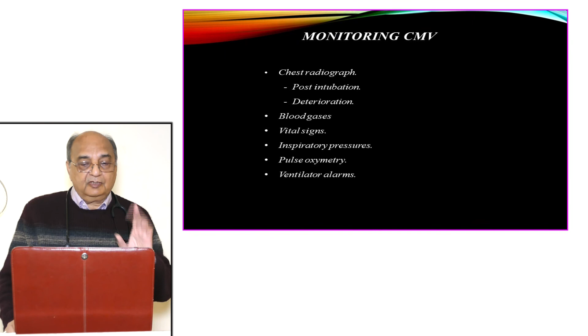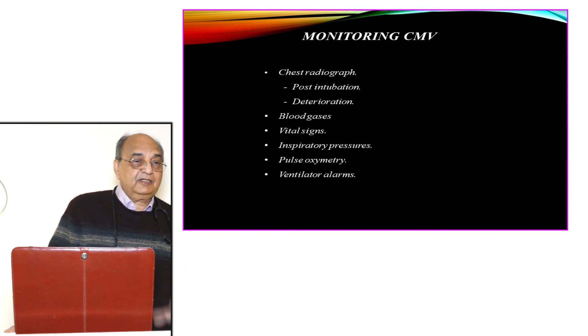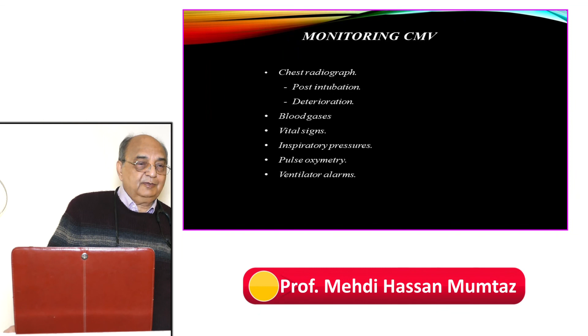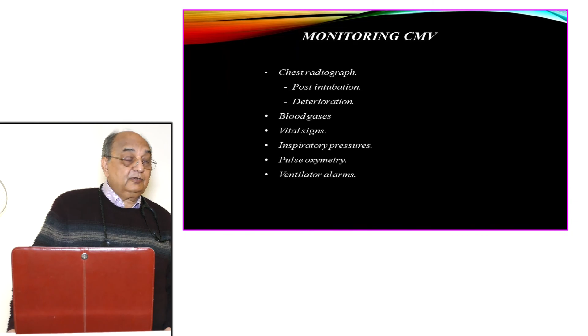To avoid these things, the alarm systems came into action. Never ever put the alarms off. Keep all the alarms on. You change the range of them, even for blood pressure, pulse, SpO2 and other things. Alarms should always be on. Then pulse oximetry will automatically tell you. Then ventilator alarms: keep an eye on them. When there is an alarm, look at what it is. Is it about oxygen? Is it about PIP? Or is it about tidal volume, or other things? You should always look at it and not ignore it.